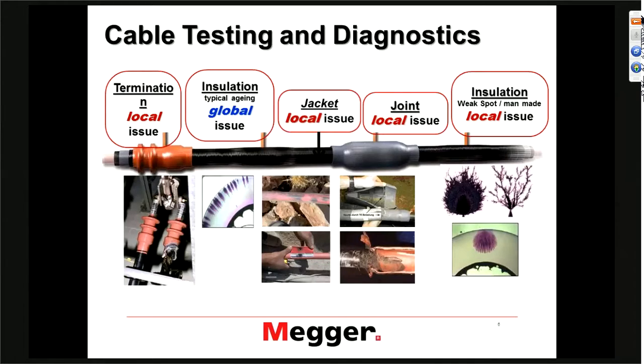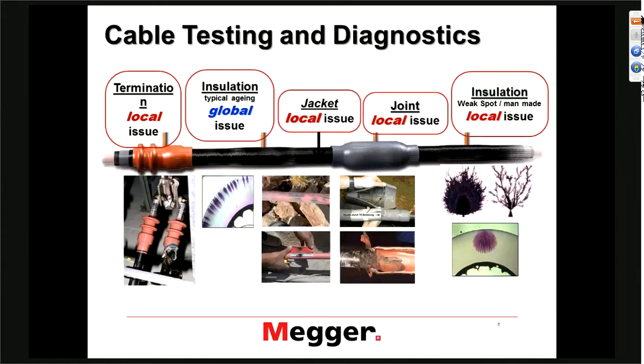Obviously, this had to do with either the insulation having some high stress point that eventually led to the formation of water trees. But if you look at that one compared to the second from the left, you see a big difference between the dispersion of these water trees — that's why one is a local issue and one is a global issue. We're only dealing with one type of global issue, which is the true aging condition of the cable, and all the local issues are pretty much related to the installation process.